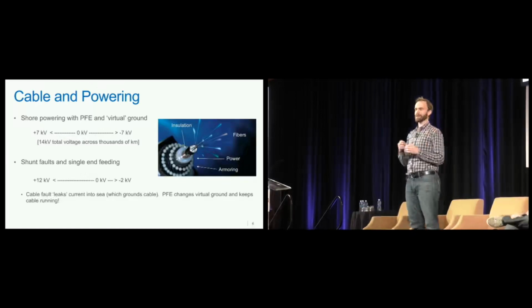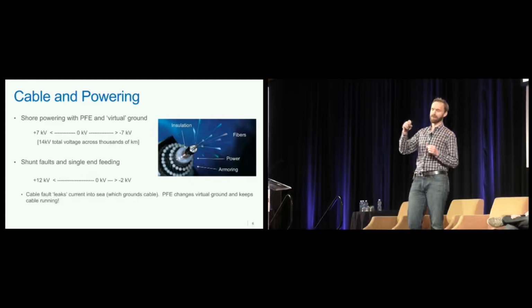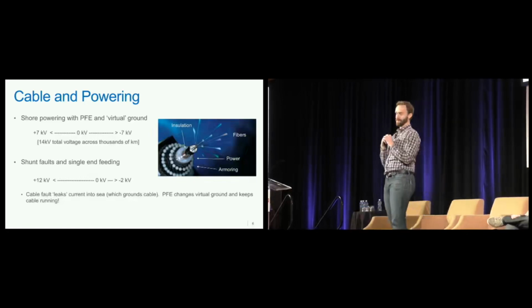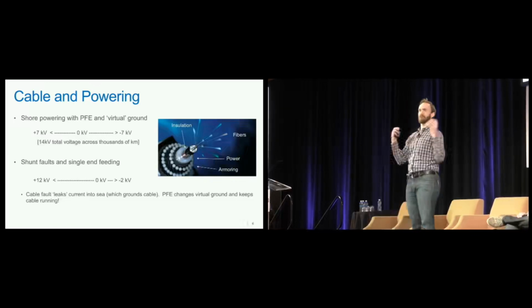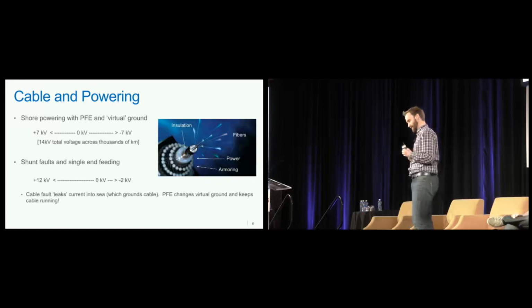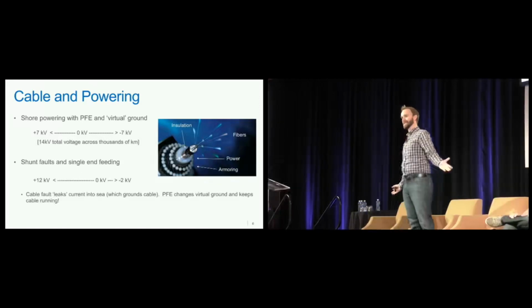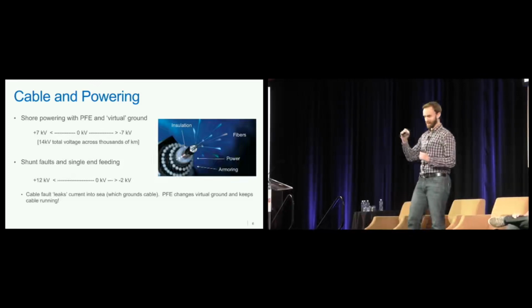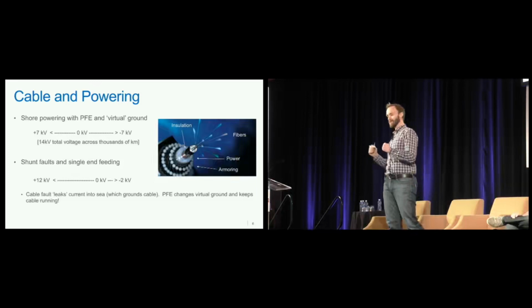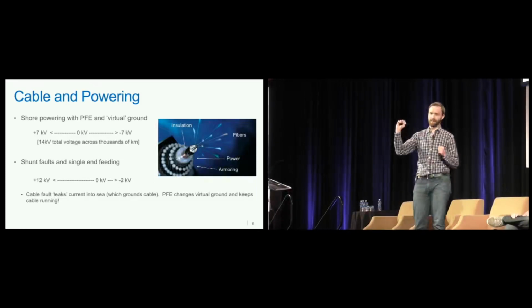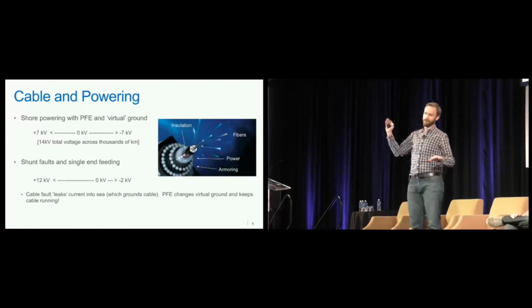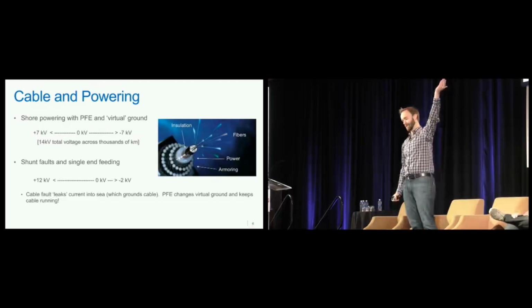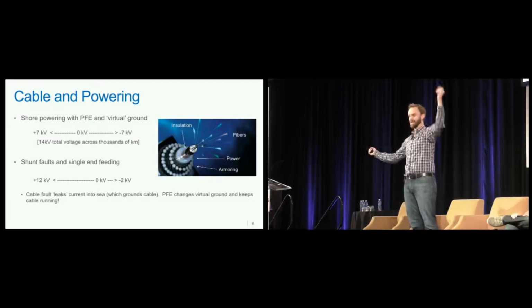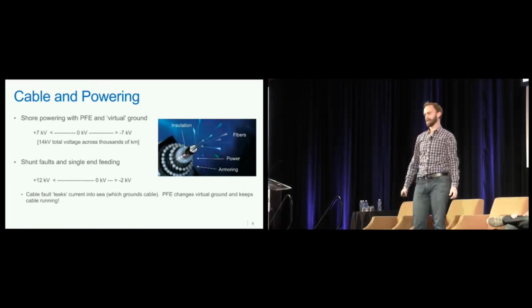One of the most common failures of a subsea cable is a tear in the sheath. Outside the armor there's a black, tarry layer that keeps water out. Over time the cable chafes, a little water gets in, and when it touches the copper, it immediately changes the ground, because the sea is a great ground. In this example, if I'm a few hundred kilometers off the coast and water gets into the cable, the PFE changes and the ground moves — one side goes up to 12 kilovolts, the other changes to -2, and a real sea ground has just been created.